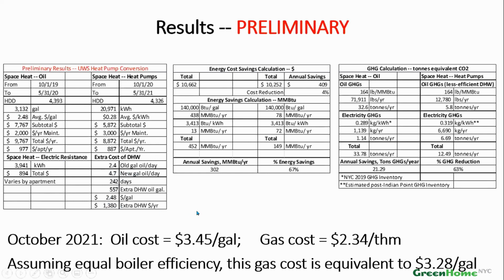But even with all that in mind, if we look at this middle figure, we see a cost reduction of 4%. And to my mind that is absolutely unbelievable. The fact that at this building, where we were averaging 10 BTUs per apartment per square foot per heating degree day, to actually come out saving money on energy straight out of the gate, I'm just absolutely flabbergasted by that. And that's without anybody really having any experience using these heat pumps.